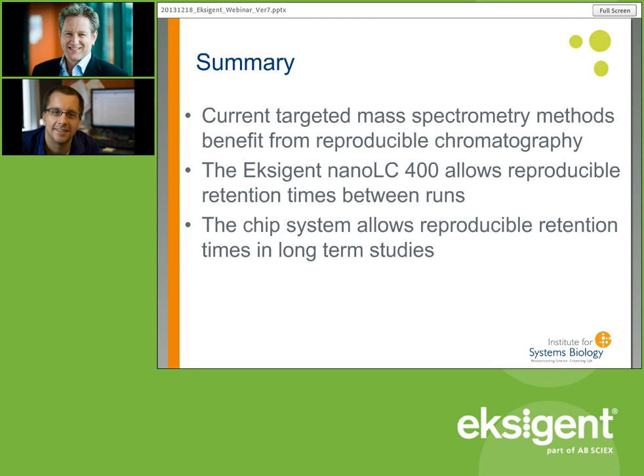There's a question about whether chromatographic retention times depend on temperature and whether you see retention time variations. Definitely, retention time will vary with column temperature. But one of the features of the ChipLC system is that both the trap chip and the column chip are temperature controlled, so we maintain a stable retention time even if the lab temperature would vary quite a bit. Another question: does it make sense to calibrate the chromatography — like what's done in glycan analysis using standards — or is the reproducibility sufficient without that chromatographic calibration?